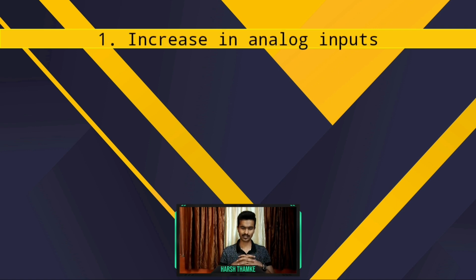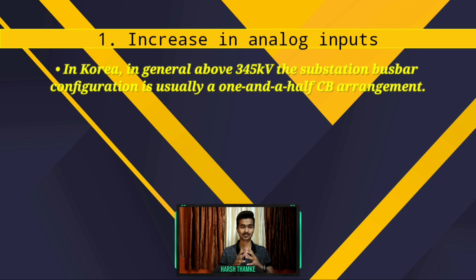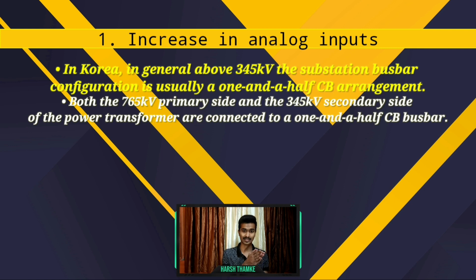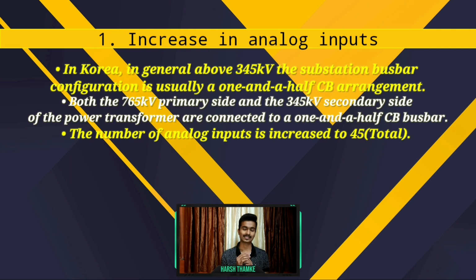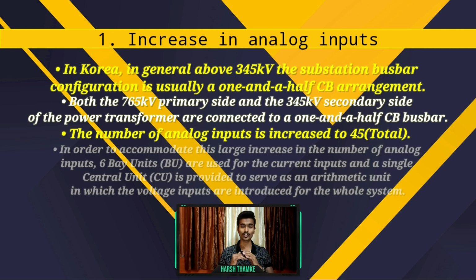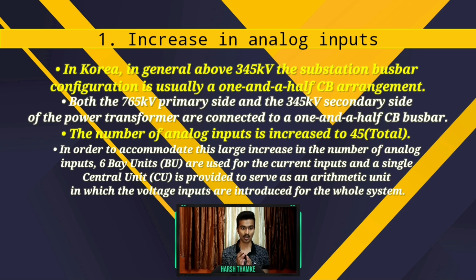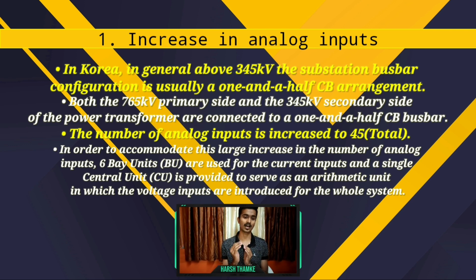Increase in analog inputs. In Korea, in general, at 345 kV, the substation busbar configuration is usually a 1.5 CB arrangement. Both the 765 kV primary side and 345 kV secondary side of the power transformers are connected to a 1.5 CB busbar. The number of analog inputs is increased to 45 in total. In order to accommodate this large increase in the number of analog inputs, 6 bay units BU are used for the current input, and a single central unit CU is provided to serve as an arithmetic unit in which the voltage inputs are introduced for the whole system.